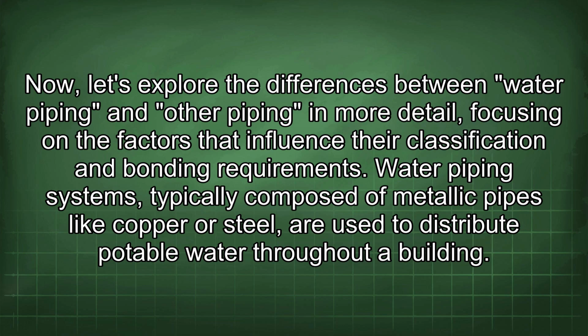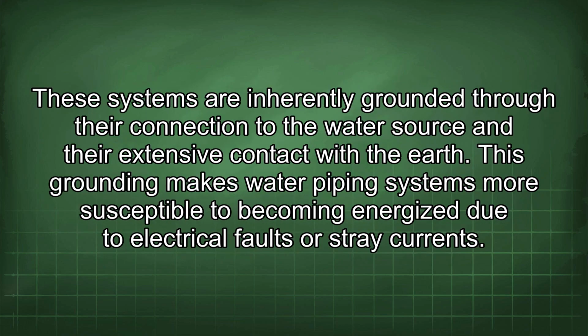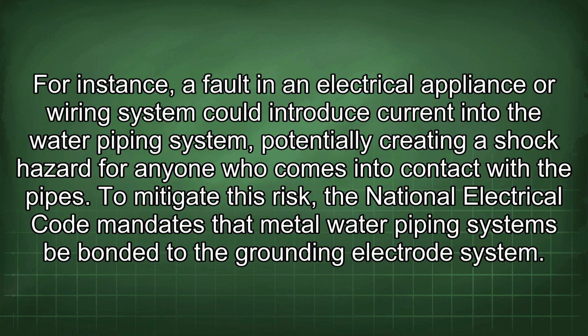Water piping systems, typically composed of metallic pipes like copper or steel, are used to distribute potable water throughout a building. These systems are inherently grounded through their connection to the water source and their extensive contact with the earth. This grounding makes water piping systems more susceptible to becoming energized due to electrical faults or stray currents. For instance, a fault in an electrical appliance or wiring system could introduce current into the water piping system, potentially creating a shock hazard for anyone who comes into contact with the pipes.